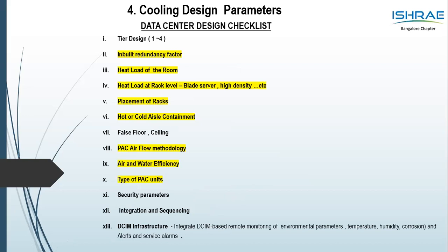Again, further breaking it down, the important design checklist on data center cooling points is, we talked about the tier design. So 1 to 4, N+1, 2N+1. Inbuilt redundancy, that's again correlated to the tier design. We will also look at the saving which is generated by having inbuilt redundancy in my coming slide. Heat load of the room, very important to understand what is the heat load from the room. Heat load per rack, what is the heat load which is generated per rack. Placement of rack, we don't want the unit to be placed at one side and the rack at the opposite side, with the required airflow not reaching the rack. We don't want that to happen.